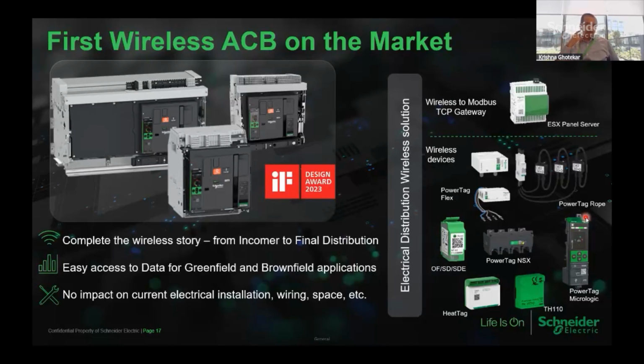On top of that, by end of this year, we will be also coming with a retrofit trip unit of MTZ of MicroLogic Active, which can be installed on NT NW install base. So which means, let's say you have a standard application where you have MasterPact NT NW, maybe 10, 15 or 20 years. Now you want to retrofit or new features. Of course, if they have the budget, they can change the moving part or complete breaker depending on the feasibility.